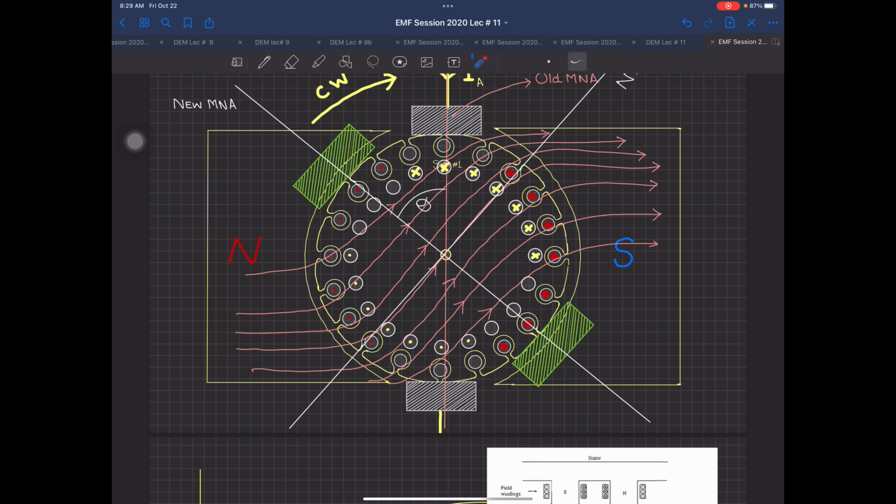So when holes are created, the effective contact between the carbon brush and this one is going to be decreased. So after some time, not maybe like 5 or 6 hours, but maybe something like 7 or 8 days, depending upon the use of that motor, the pitting of commutator segments is going to take place. Pitting means holes are being created. Those holes are being created because of the sparking taking place. A lot of high temperatures are being created over there. Now this is one problem: sparking taking place, pitting of commutator segments taking place.